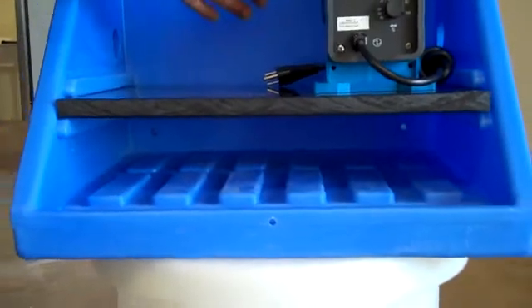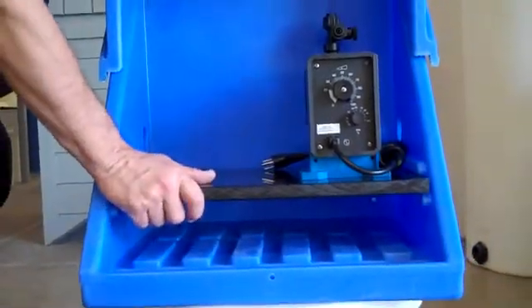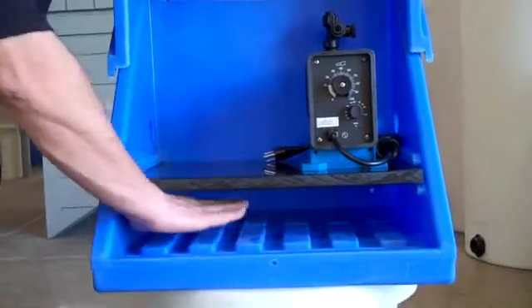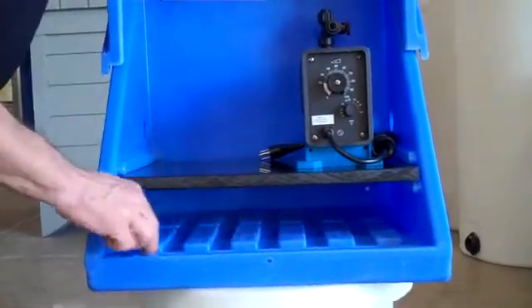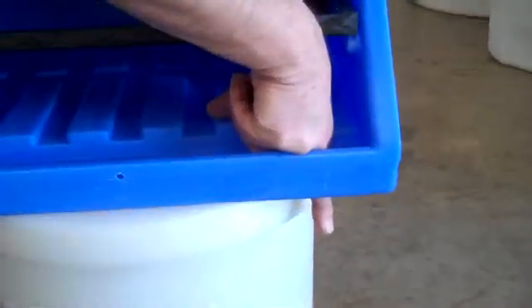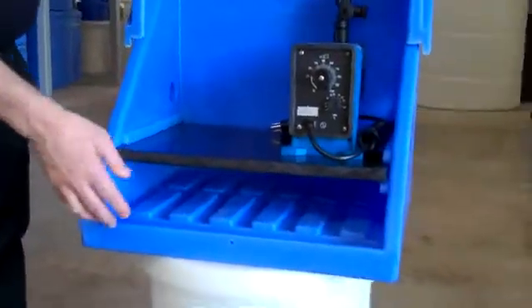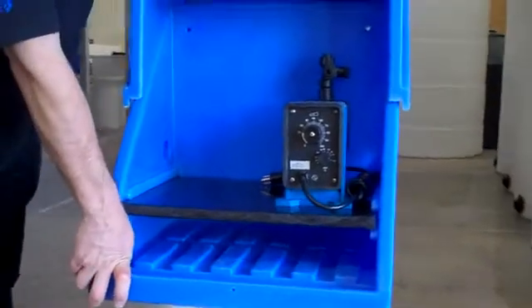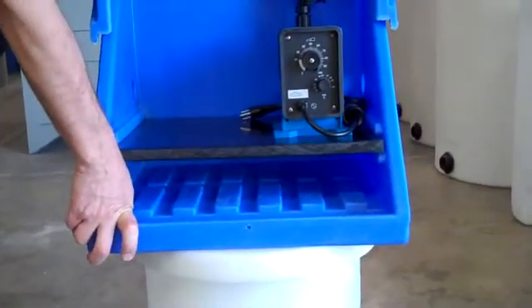It has an opening in the bottom to allow for any spilled chemical from leaking tubing or a broken diaphragm — anything that happens to a pump. This will contain the liquid in the bottom and channel it out into the canal on the front. You can connect the opening here — I'm going to stick my finger through it — it has a threaded connection on the bottom, and you can run a piece of tubing from this into a drum, back into the chemical tank you're pumping from, or any other safe place to dispose of your chemicals so they're not exposed to the environment.